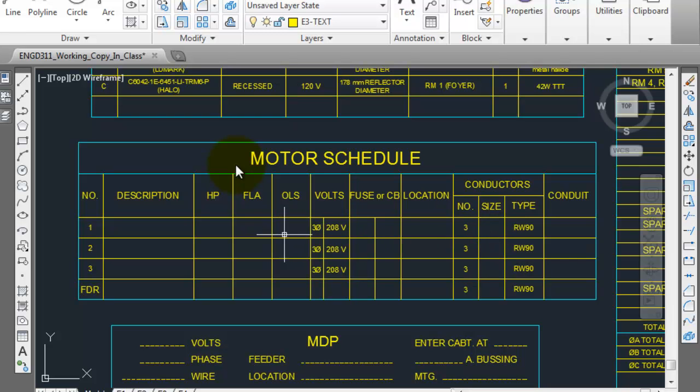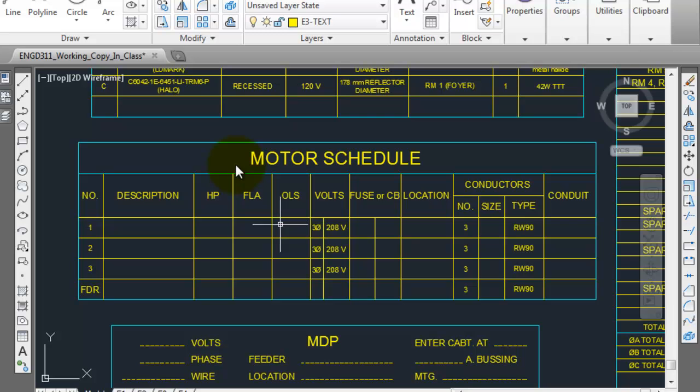So if you determine from the OLS value that you've got, I don't know, 30.5 amps, you're going to look in table number 2 and you're going to find an American Wire Gauge size that will allow you to run 30.5 amps safely. And so I'm just looking on my list here, I see number 8, so this is going to be number 8.